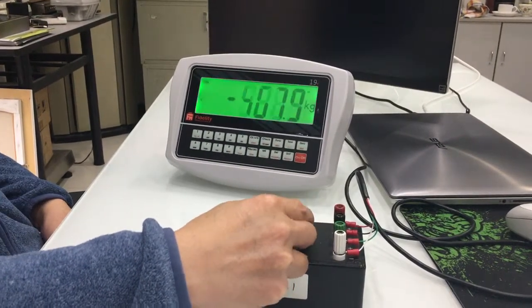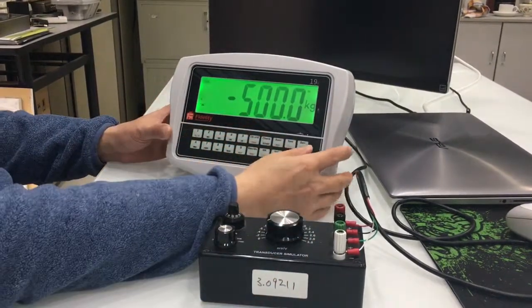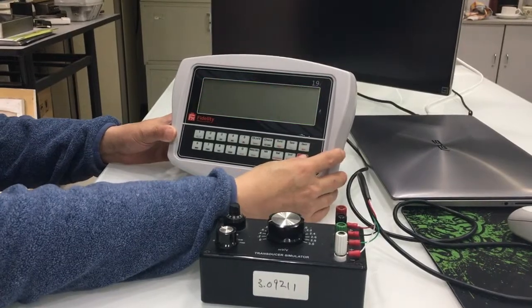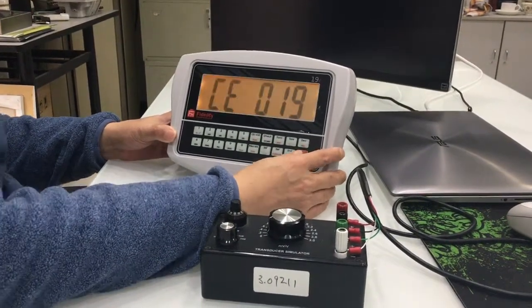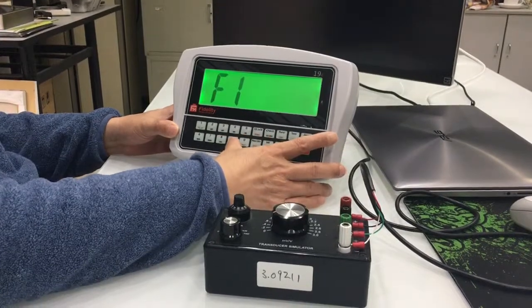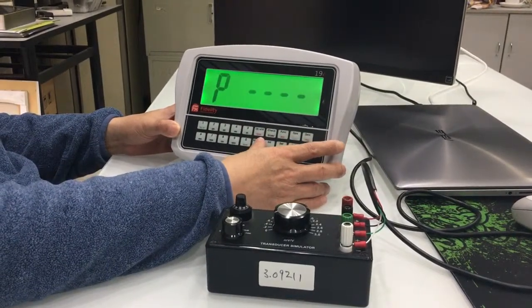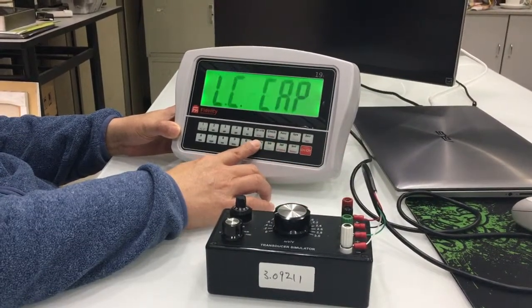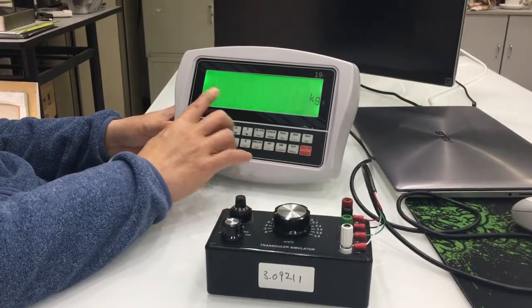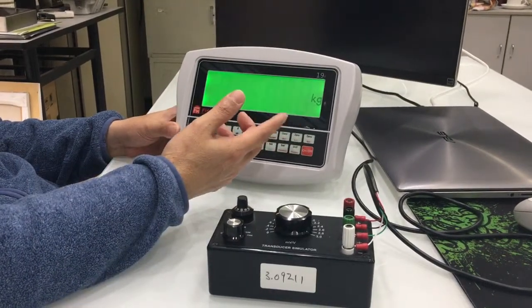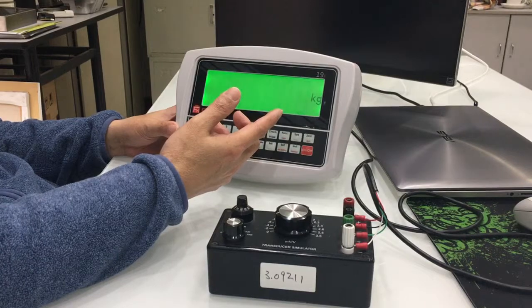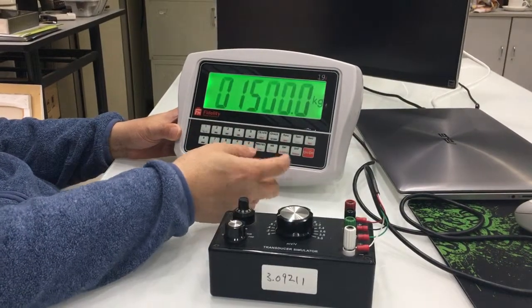We are going to correct this with this newly created calibration method. First of all, I go to internal function 90, press enter, enter the password. Then the first step is to enter the load cell capacity here.